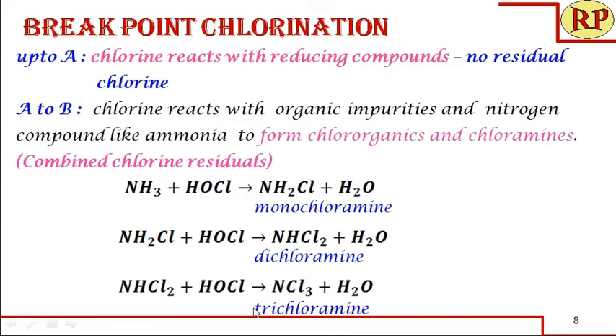Beyond C, the total residual chlorine — including free and combined chlorine — acts as a disinfectant to kill the pathogens. Breakpoint chlorination is also important for swimming pools, because swimmers incorporate a lot of nitrogen compounds into the water. The more swimmers, the more nitrogen is added in the form of urea, due to sweating, secretions like sweat and urine, and body oils. Swimming pools need to continuously monitor breakpoint chlorination to ensure the water remains free from pathogens.